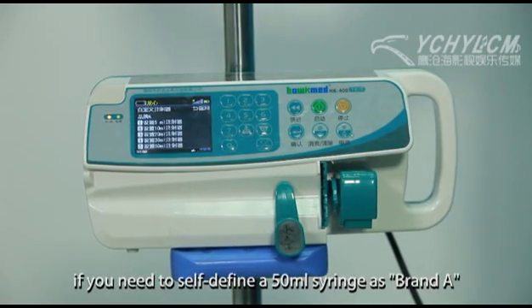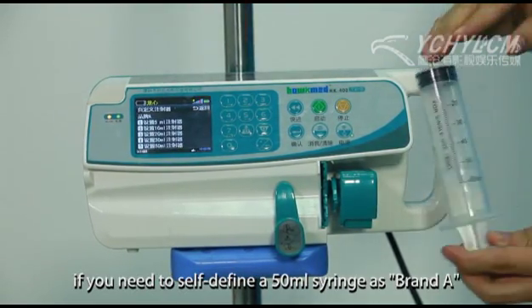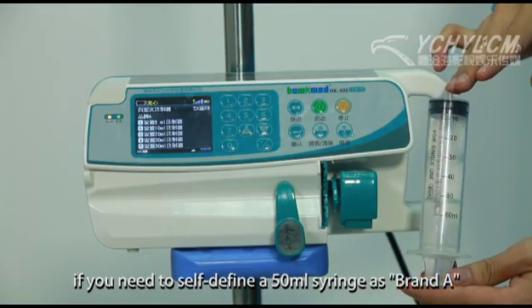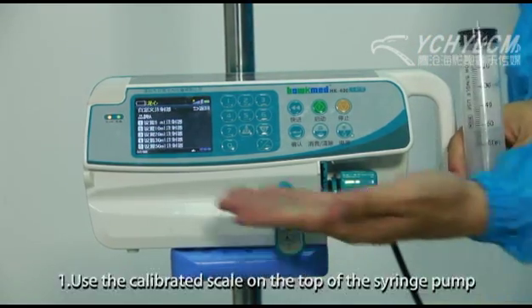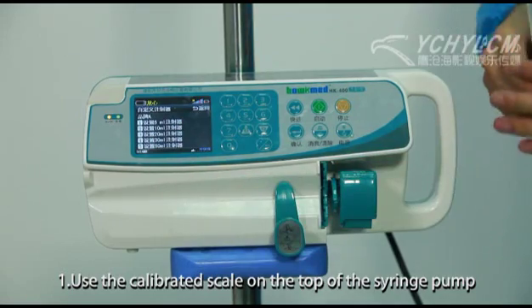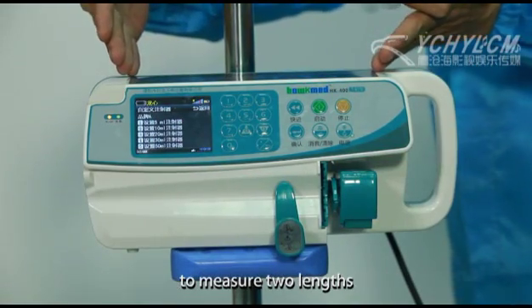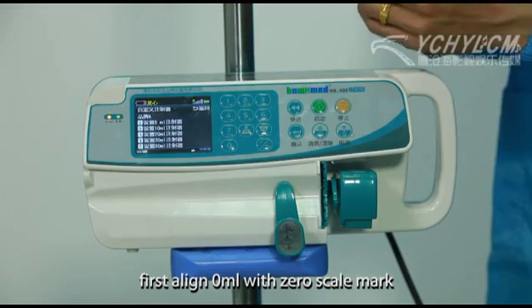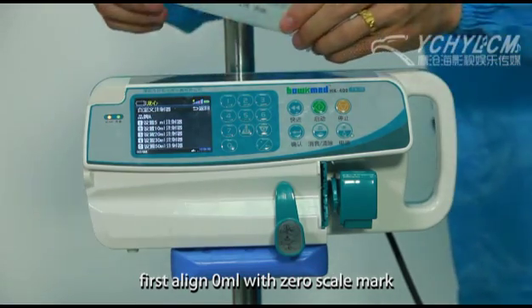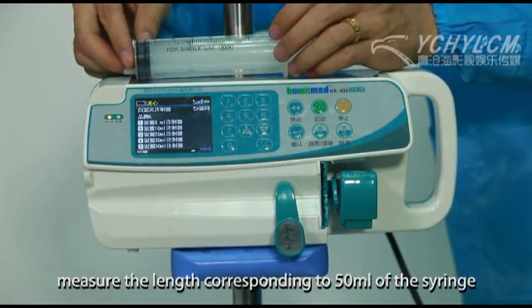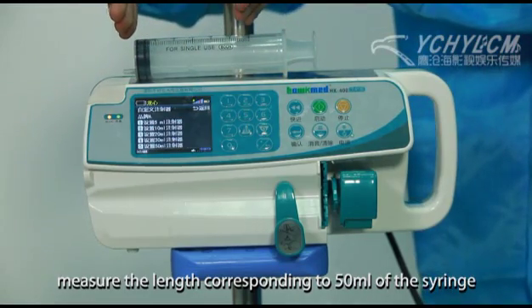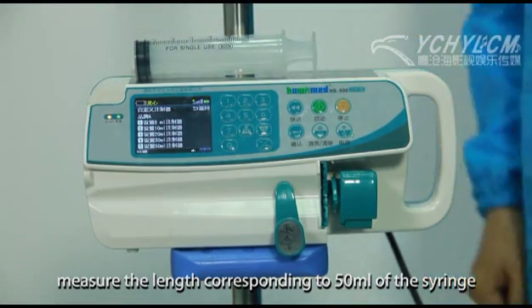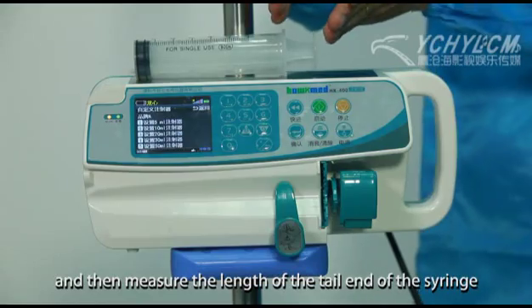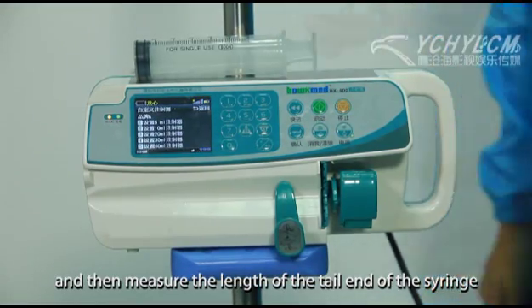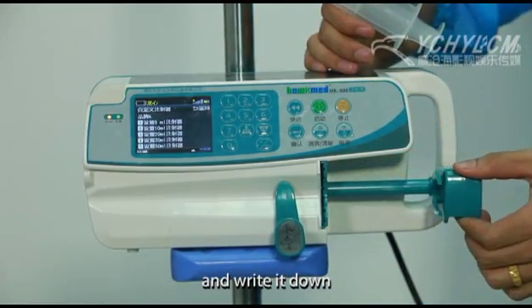For example, if you need to self-define a 50 milliliter syringe as brand A, you should: 1. Use the calibrated scale on the top of the syringe pump to measure 2 lengths. First, align 0 milliliters with 0 scale mark. Measure the length corresponding to 50 milliliters of the syringe and write it down. And then measure the length of the tail end of the syringe and write it down.